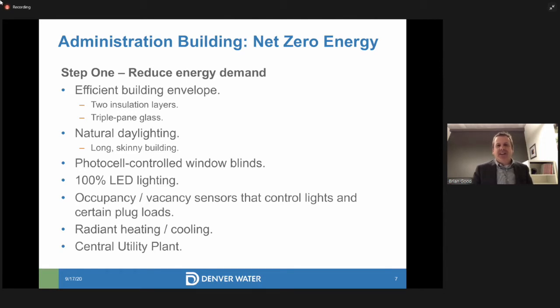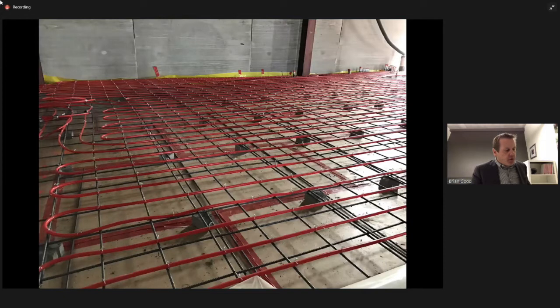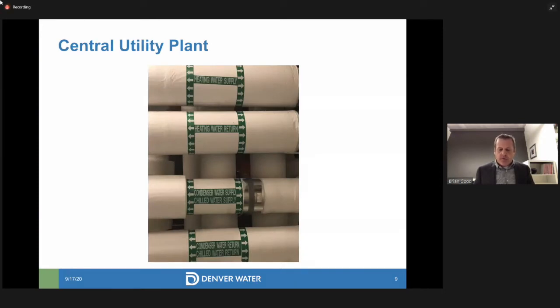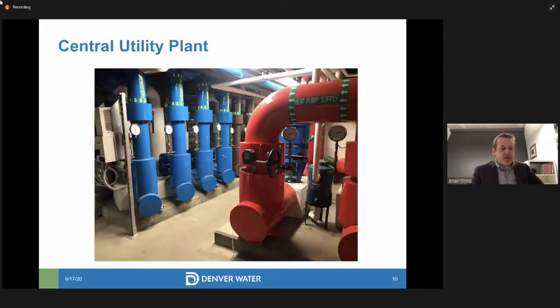There's radiant heating and cooling throughout, as well as a central utility plant that I'll talk a little bit more about. This is a photograph of radiant tubes being installed prior to concrete placement, and all but one of the new buildings is both heated and cooled through an in-floor, or in some cases, an in-ceiling radiant system. Now, those radiant tubes are fed from a four-pipe loop that originates from an on-site central utility plant. So there's a heating water supply and return, as well as a chilled water supply and return. Now, this is an incredibly efficient system, which actually uses potable water from a 54-inch water main as a heat sink. So it's very similar to a geothermal well field, but without all the wells.